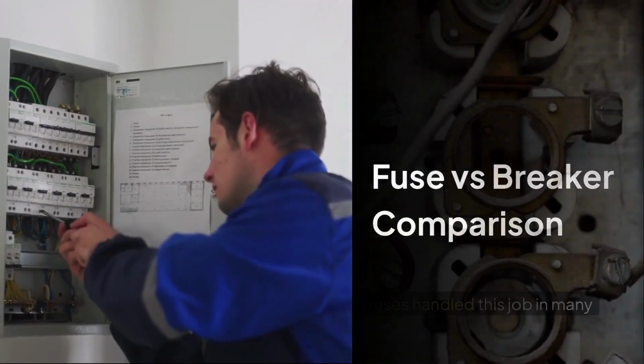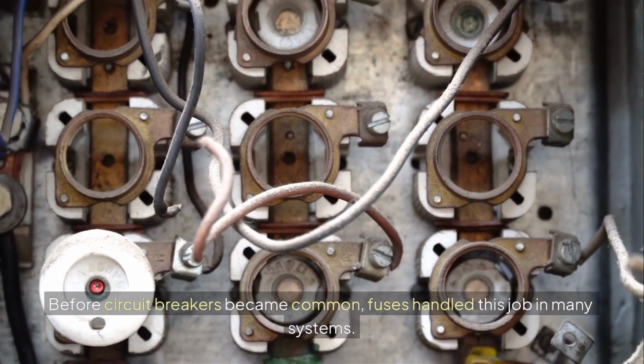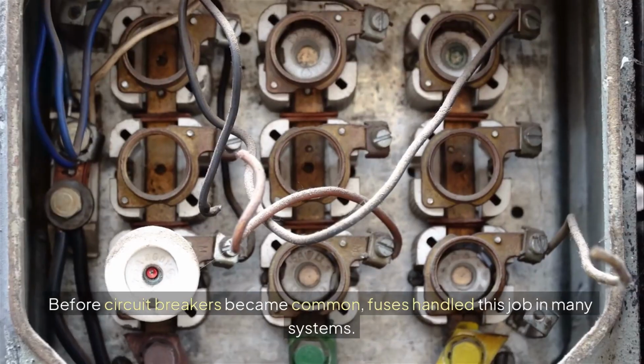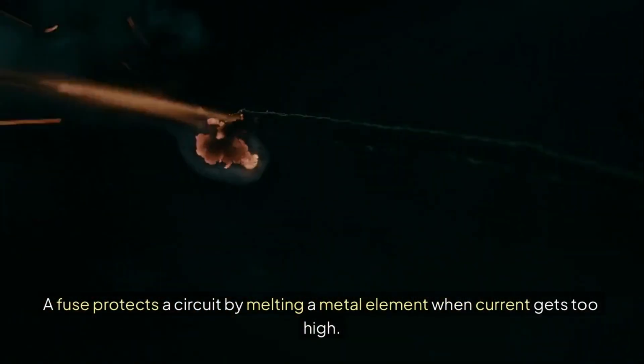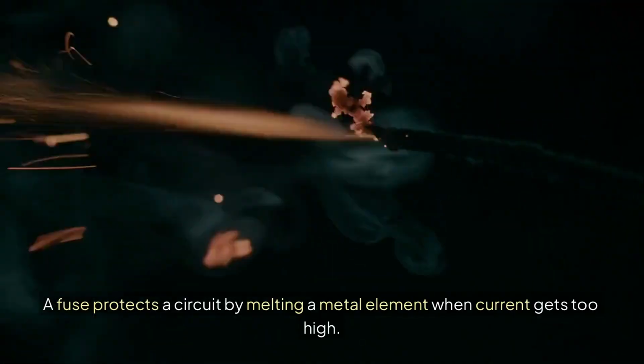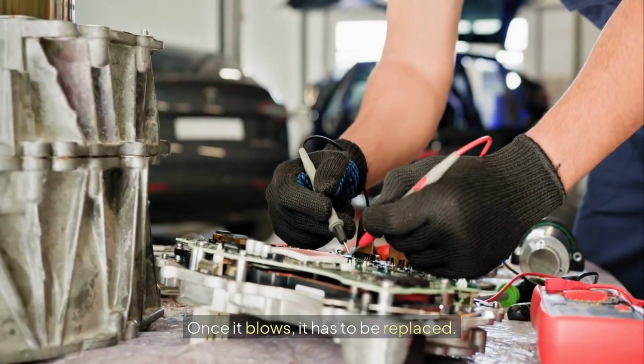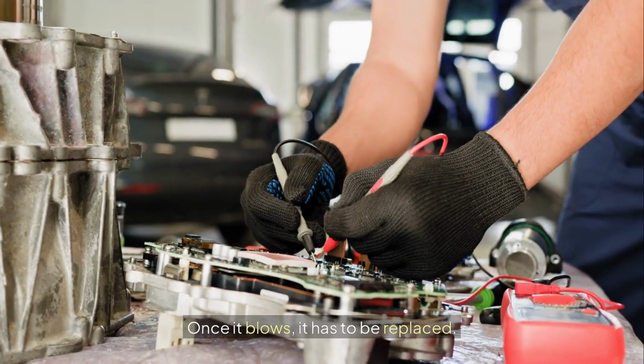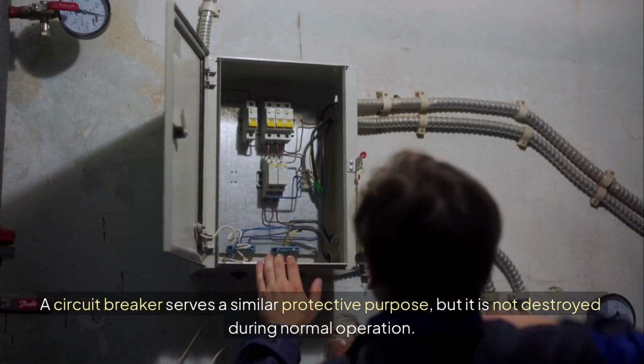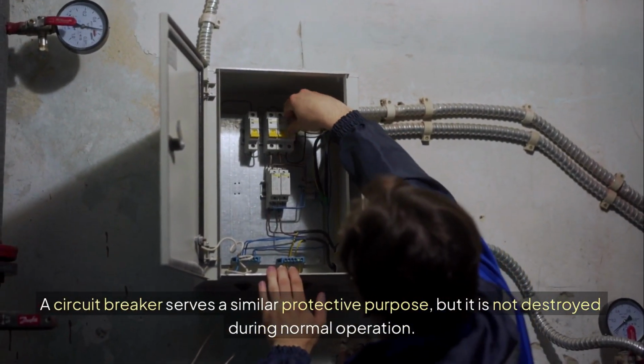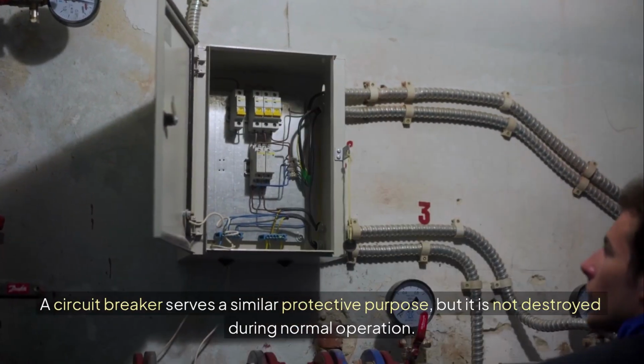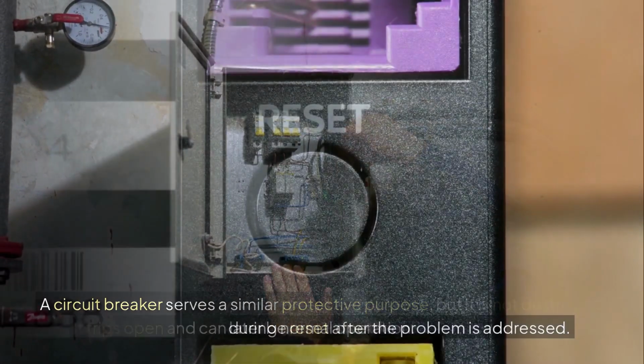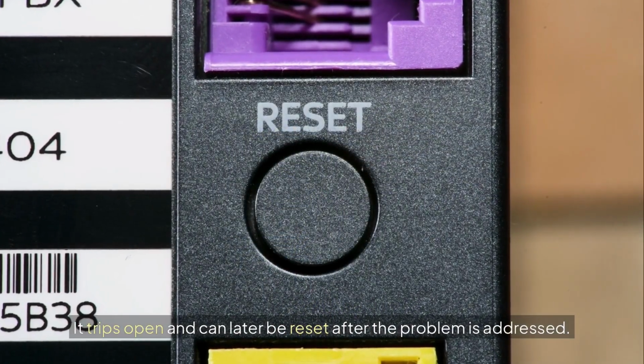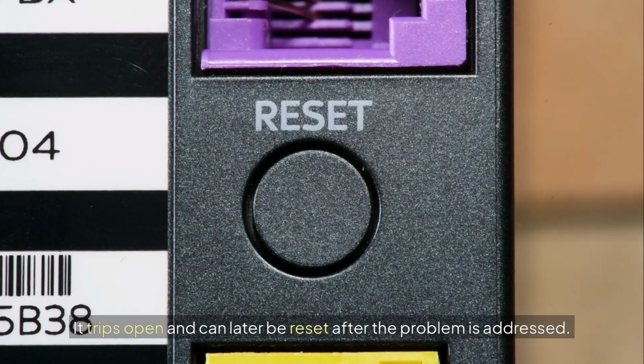Fuse versus breaker. Before circuit breakers became common, fuses handled this job in many systems. A fuse protects a circuit by melting a metal element when current gets too high. Once it blows, it has to be replaced. A circuit breaker serves a similar protective purpose, but it is not destroyed during normal operation. It trips open and can later be reset after the problem is addressed.